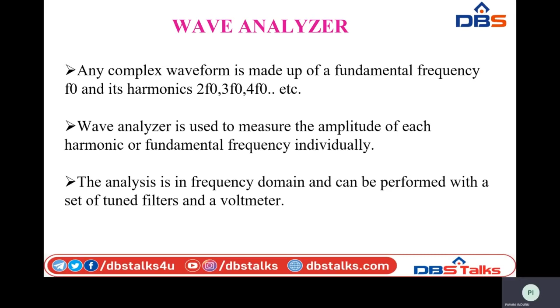Wave analyzers are also referred to as frequency selective voltmeters, carrier frequency voltmeters, and selective level voltmeters. So why these names? Here, those wave analyzers are tuned to a certain frequency. For example, if you want the wave analyzer to tune to twice the fundamental frequency, 2F0, then the wave analyzer is adjusted to that frequency.